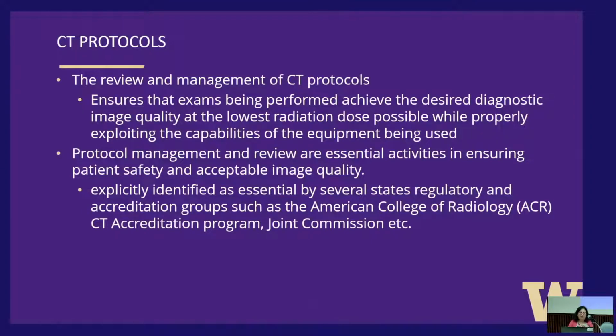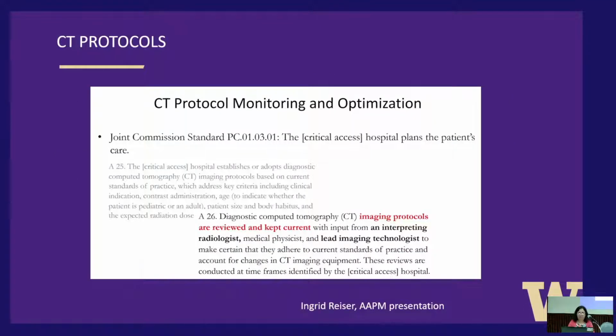And the reason they've started doing this, and it's probably been around now for the last maybe 10, 15 years, is because exactly that you do not want to set up a protocol, forget all about it, because it's changing with the needs of the patient population and the needs of the radiologist. So you need to review and manage it on an annual basis, to make sure you're giving the right amount of dose to the patient.